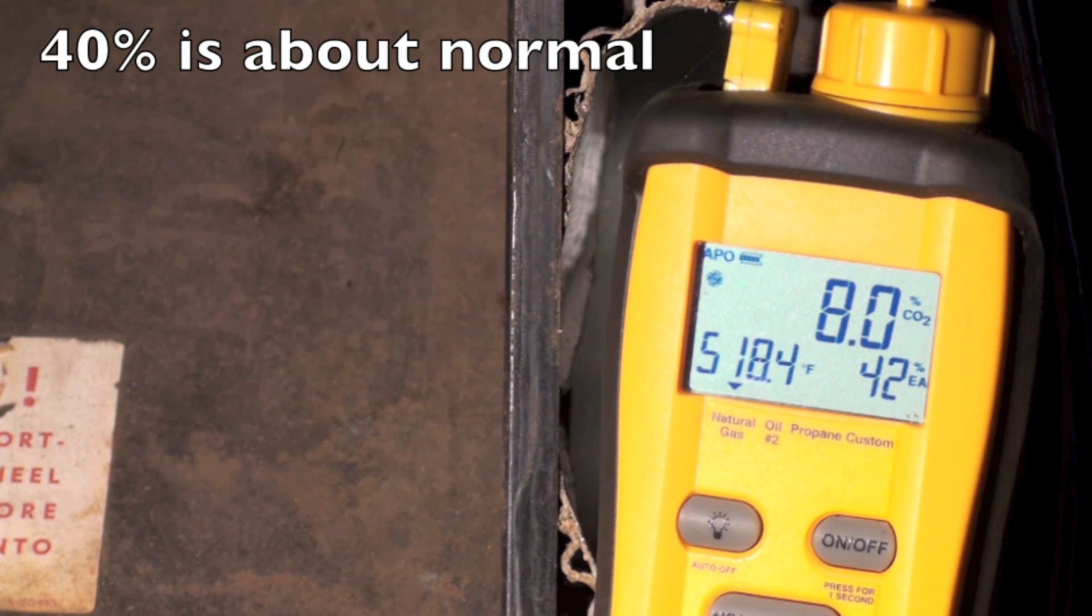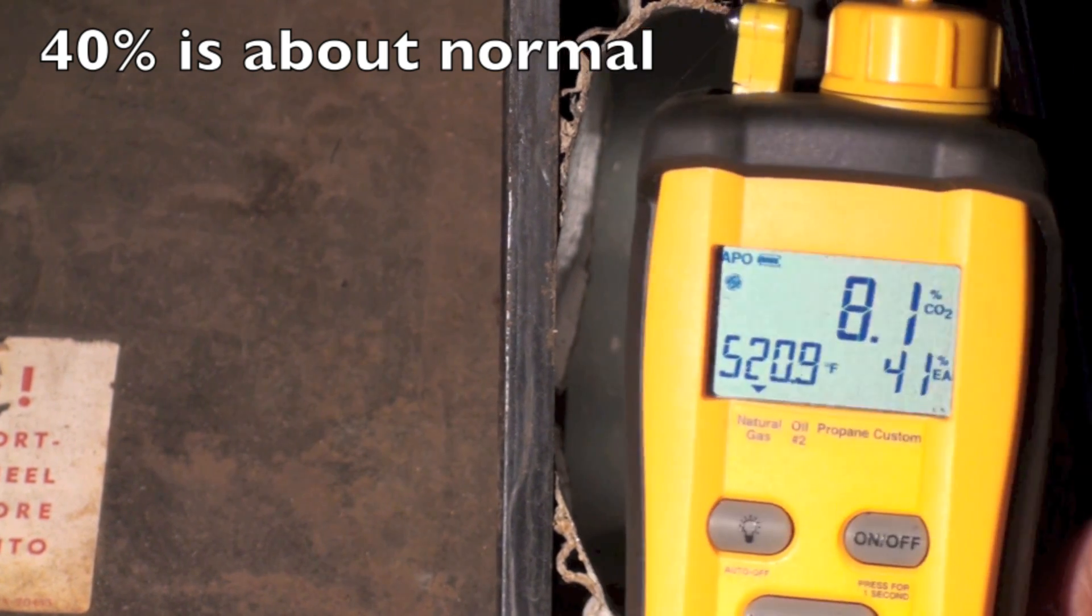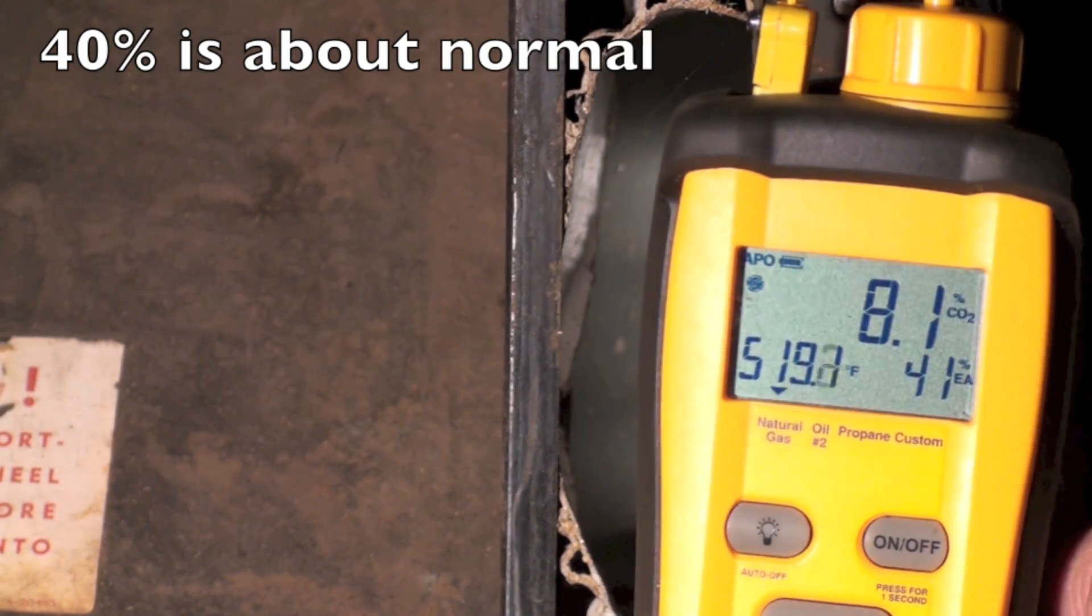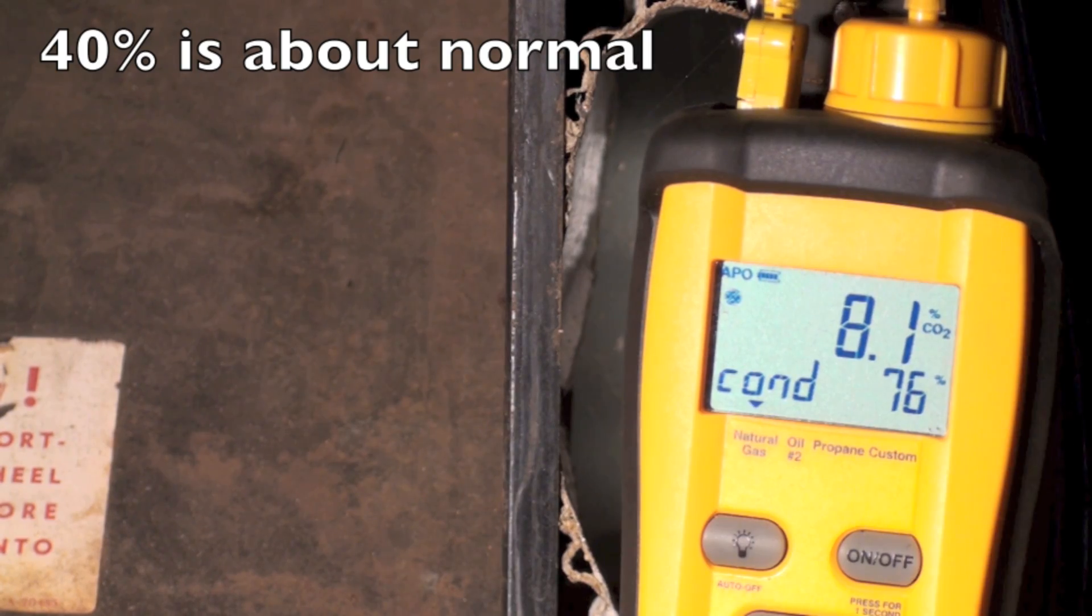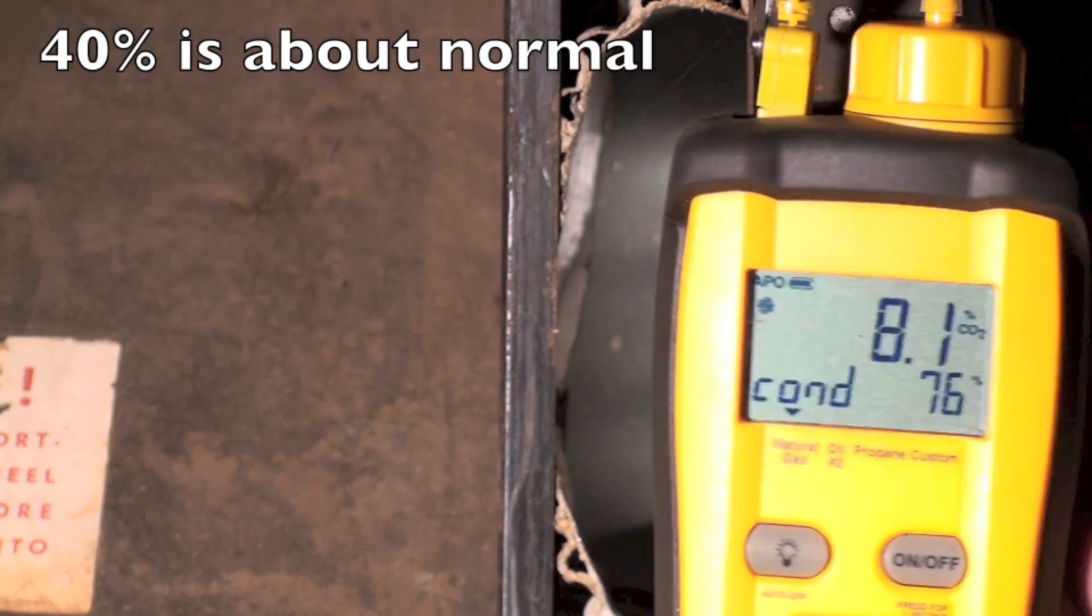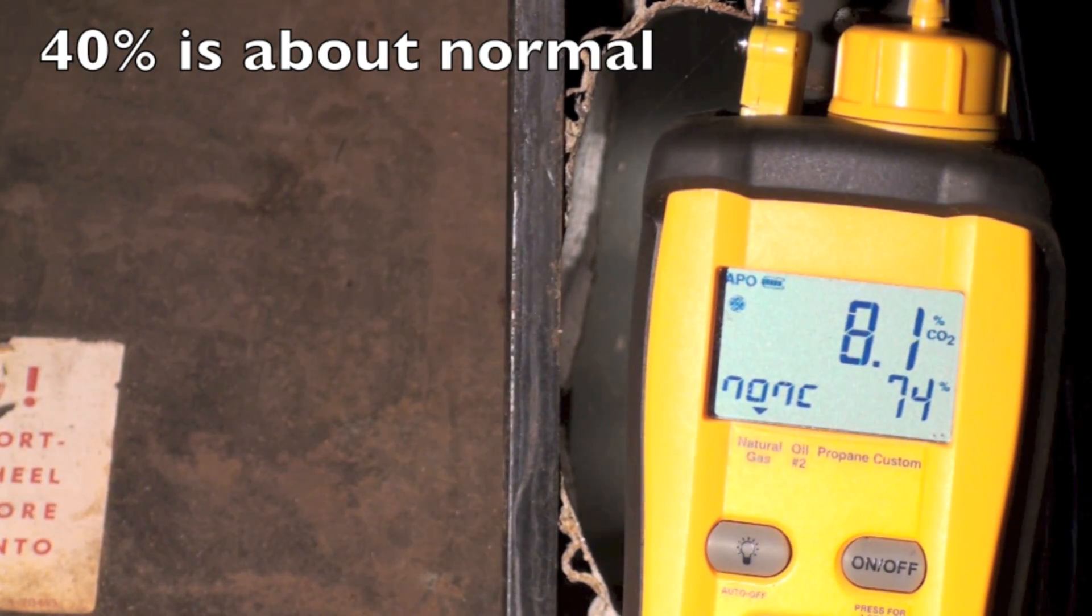So there's 40%, 42% more air than is necessary for combustion. Okay. Now let's go down and look at efficiency. We'll get to non-condensing, and we're at 74%.